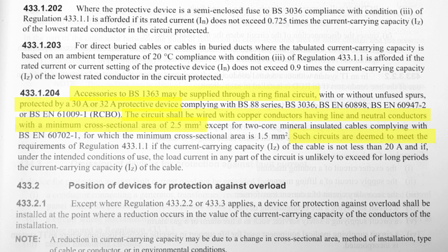Such circuits are deemed to meet the requirements of Regulation 433.1.1 if the current carrying capacity of the cable is not less than 20 amps and if, under the intended conditions of use, the load current in any part of the circuit is unlikely to exceed for long periods the current carrying capacity of the cable.